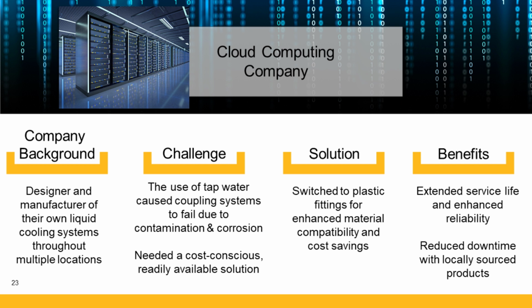So the third example concerns a cloud computing company. This company designed and built their own liquid cooling system, and they installed it in different locations. They used tap water and experienced quick disconnect coupling failure and leakages due to contamination, mainly lime scale buildup and corrosion. In this case, the mix of different metallic materials in the presence of water was creating galvanic corrosion, and some of the components were corroded and created some contamination.